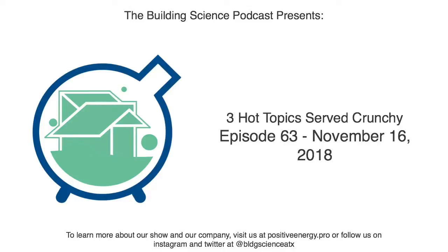Yeah, so it's interesting. I hear at our positive energy headquarters, our enclosure is just a suggestion. As you know, you've been here. Very air leaky, ACH50 of 14. And we recently got one of the Panasonic EV10s. What we're doing is we have the incoming CFM set as high as it would go, which is 100 CFM. And the outgoing, I think it's around 50 now, maybe a little bit higher. But even on this enclosure, that gives us a fairly consistent 1.5 to 3.5 Pascal pressurization. And the range, I think, is from when it's windy out or not windy out. I've been really pleased that it could handle this enclosure.